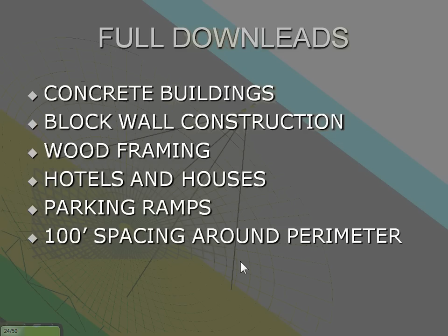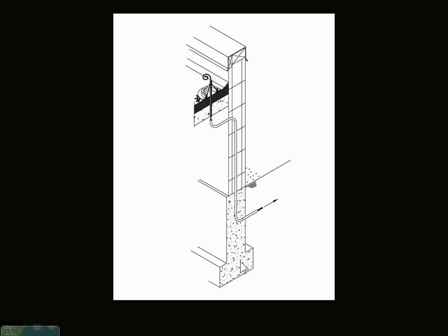Typically that's how we try to install it, and I think you have some CAD details of what that looks like in your system. This is a boot usually provided by the roofing contractor. What we do is run PVC in the wall to try to hide it, then get out to ground. That gives the lightning protection system a safe path to ground, buried in the wall. Even though it's inside your building, lightning dissipates so rapidly that you don't have to worry about any issue with lightning on the inside.